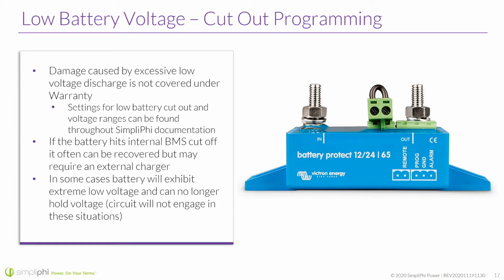Damage caused by excessive low voltage discharge is not covered under warranty. Settings for low battery cutout and voltage ranges can be found throughout SimpliPhi documentation. If the battery hits internal BMS, battery management system, cutoff, it often can be recovered, as I mentioned earlier, but may require an external charger. So what I mean by that is if the battery is dropped so low that it's unable to basically support the capacitors of the charging equipment, the inverter charger, the charge controllers, you might need to get a plug-in charger, something that can plug into an AC source and charge the batteries directly. Not always the case. Sometimes a simple BMS reset will work, but if you've dropped it well below its actual threshold, you might require that.